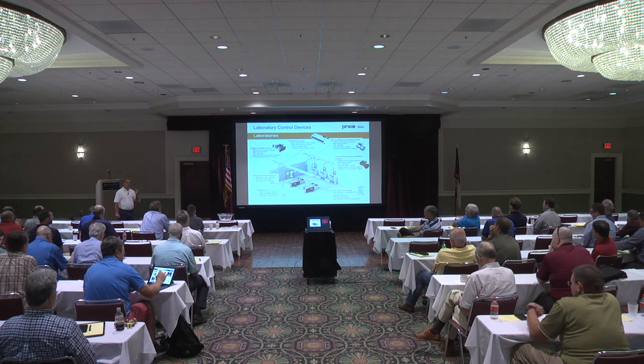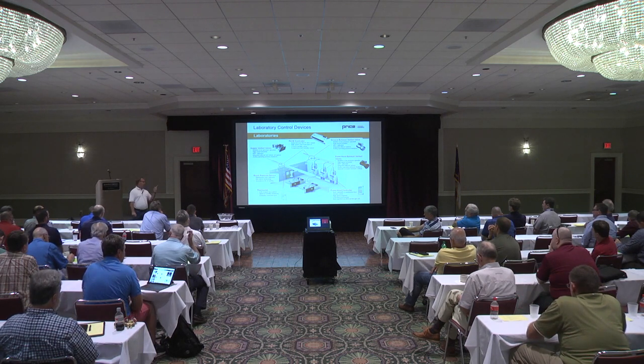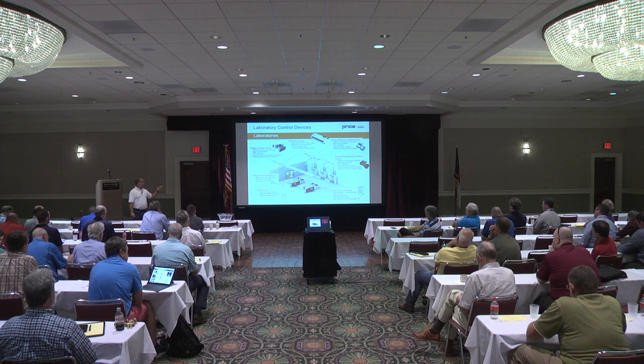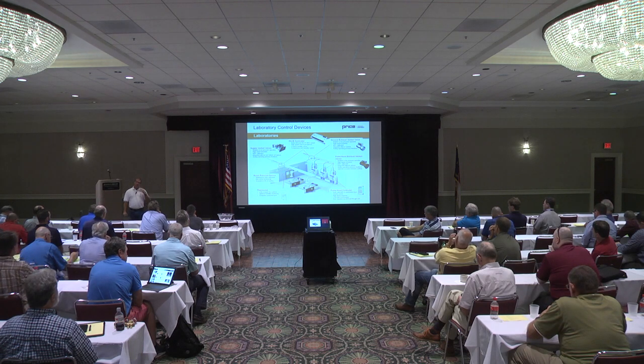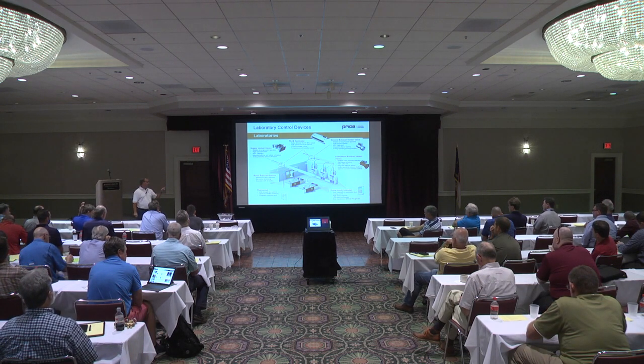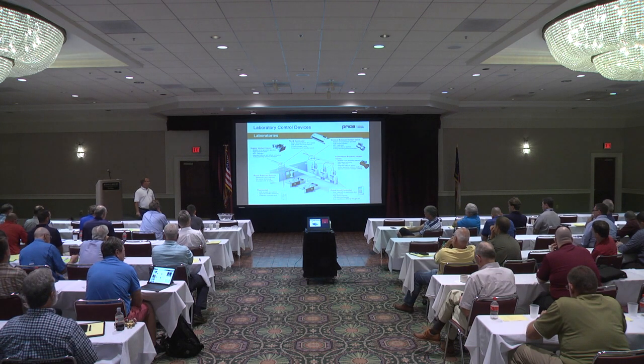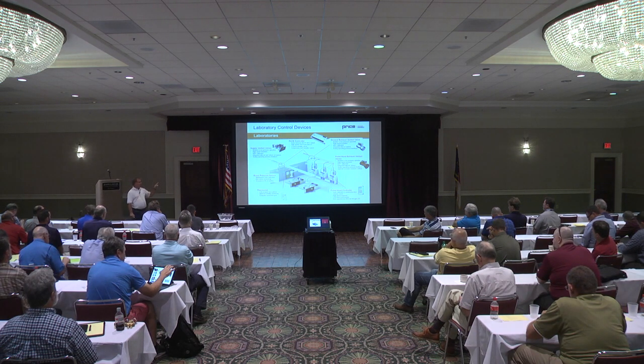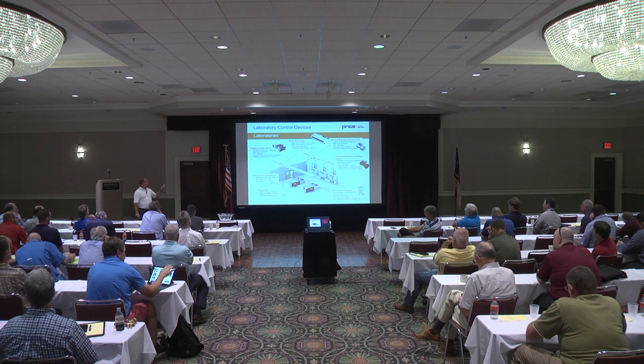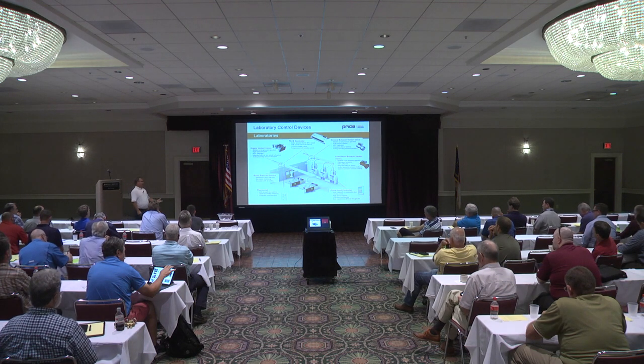The fume hood is the most important component in the lab space. If the sash is open, the valve will be open, the airflow will increase to make that fume hood safe, and the supply air will increase to maintain pressurization. Temperature control becomes the least priority because I'm not going to change the volume of air coming into that space based on someone being hot or cold. The fume hood needs the air, the fume hood's going to get the air, and then we'll reheat to maintain temperature. So this has 3 fume hoods.